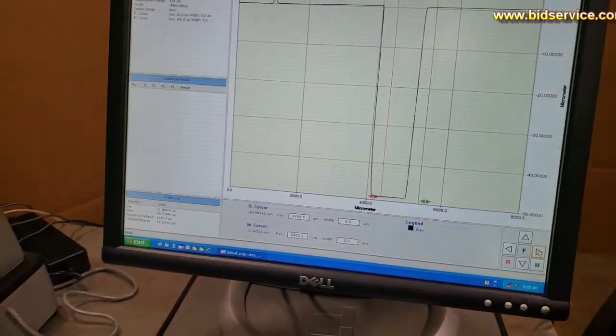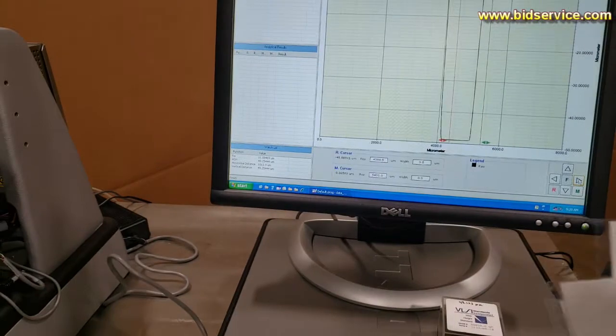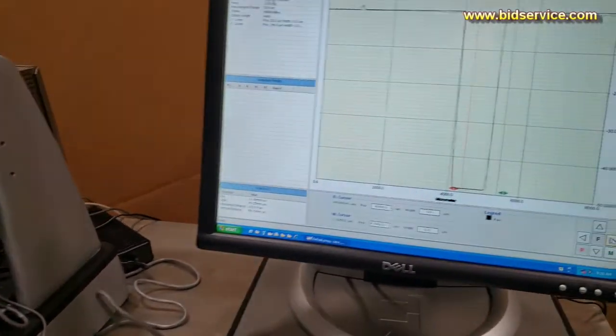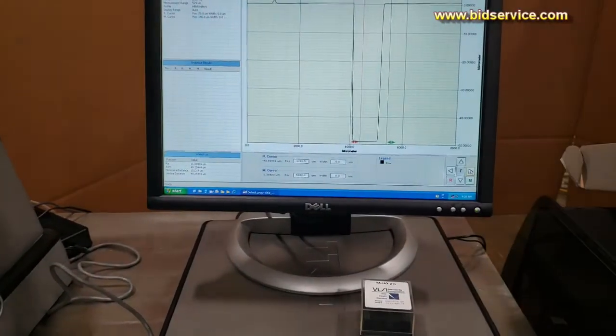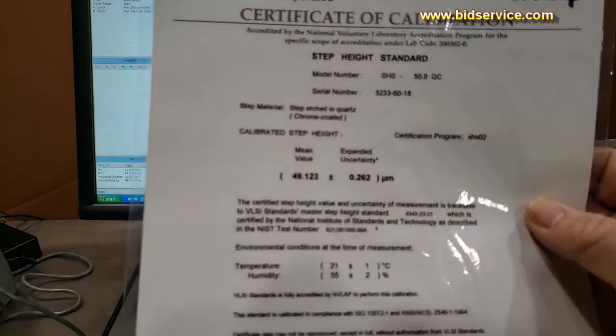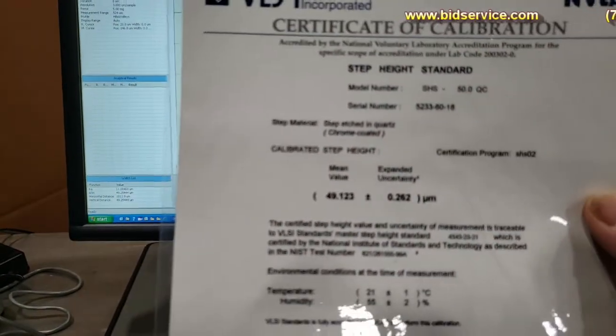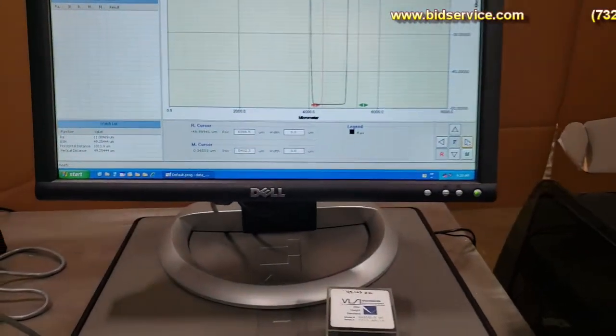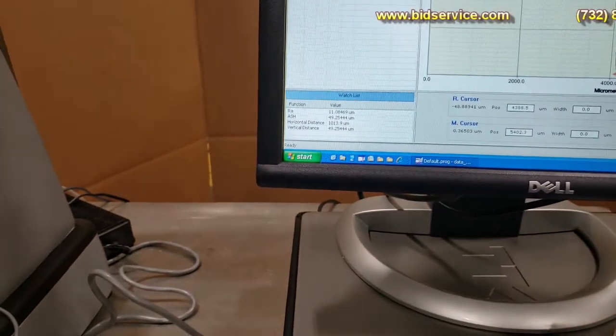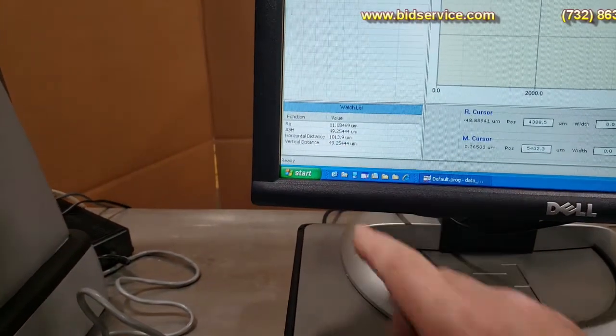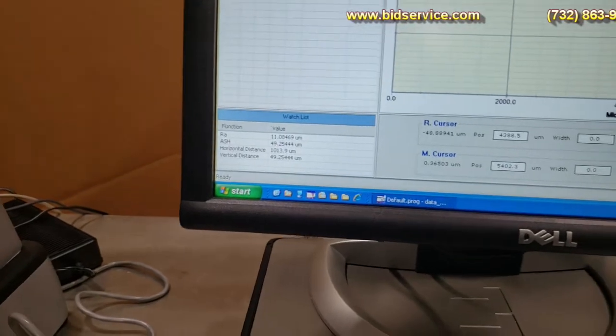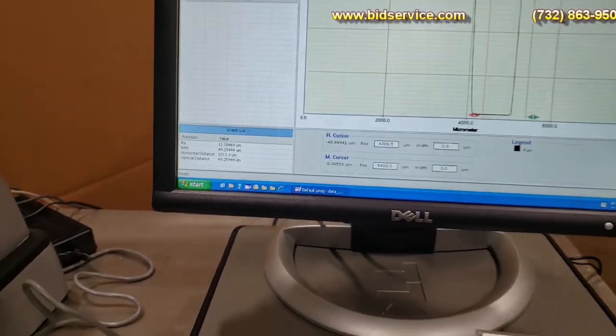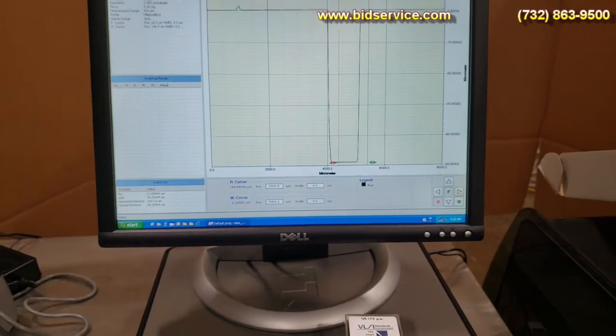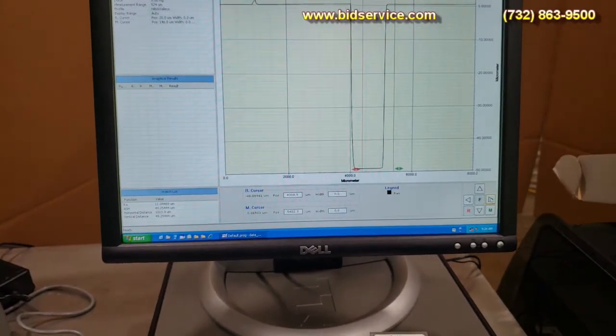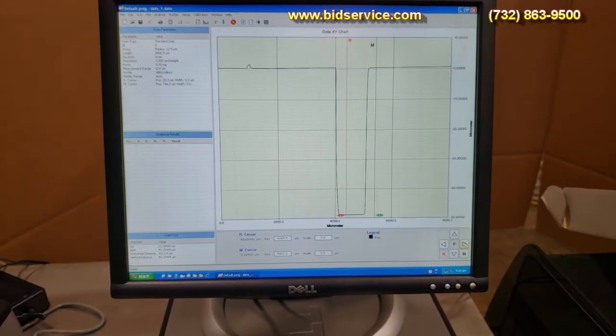Looking at the calibration sheets, this is your 50, and right there, a little bit to the left of my thumb, it tells you it's 49.123. And this is reading right now like 49.254. Next, I'm going to do the other sample. I'll do the 8. Just give me a second and I'll be right back.